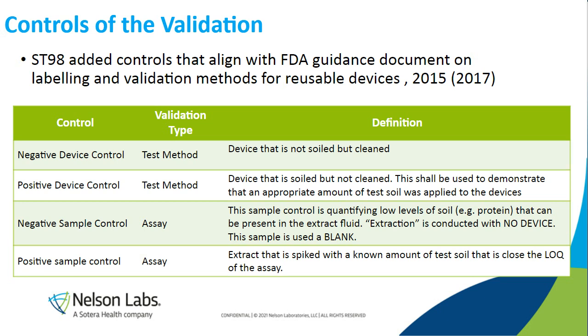The positive device control, of course, is a device that is soiled and tested side by side with the test samples. It gives you a starting assurance of what the soil components are on this product after soiling, and after reprocessing it, what is left over. So this is a test method control, and it's a required control for sure. The negative sample control is just blank, basically. It's just a blank to show that the equipment and supplies that were used during the processing of these devices were free of any contaminants that would interfere with any of the analyte assays that we're going to use.